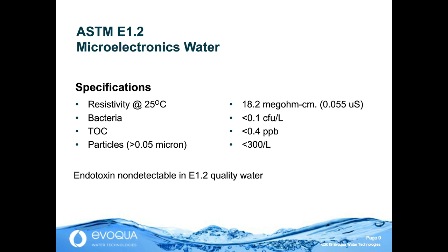And the note about endotoxin non-detectable: many years ago it was thought that endotoxin could be good to detect early micro problems, perhaps faster than micro incubation methods. That thought failed because in all of the tests run on the membrane-based electronics water, the endotoxin was non-detectable, so it could not be used to trend. So these are all membrane-based systems producing water of far tighter quality than WFI.